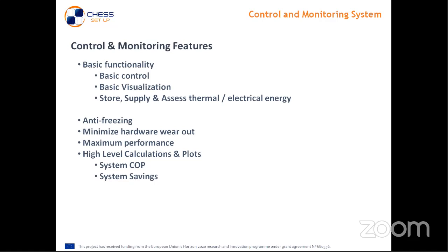The system is also designed to maximize performance by delivering energy directly from the tanks whenever possible, using the heat pump only when required. It also works at the lowest temperature possible in the PVTs to maximize electrical performance and minimize thermal losses. So for instance, if the tank is at 15 degrees, we keep the PVT production at a delta T of 5 degrees above this temperature, so at 20 degrees. If the tank is at 30, we will operate the PVTs at 35.